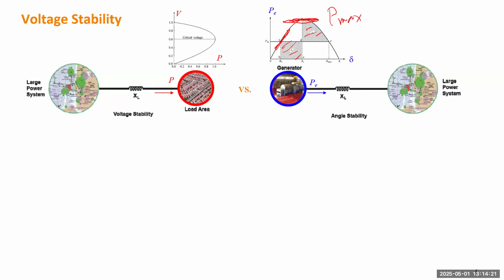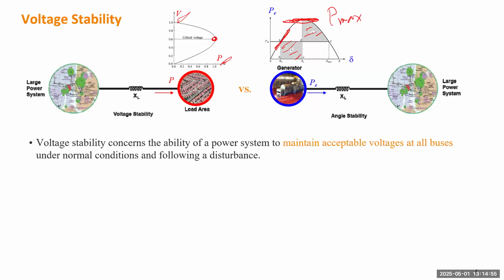But on voltage stability, we study how the voltage changes with the power. So when the power increases, the voltage can decline. What happens here is that suddenly, when the operating point passes this critical point, there's no way you can bring the voltage back unless you do very aggressive control, like load shedding or some other emergency control to save the voltage. So it will be using a different curve. We're going to talk about this curve.